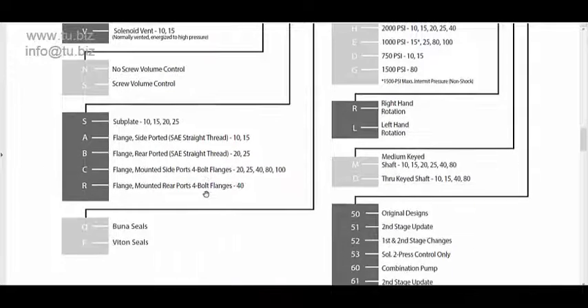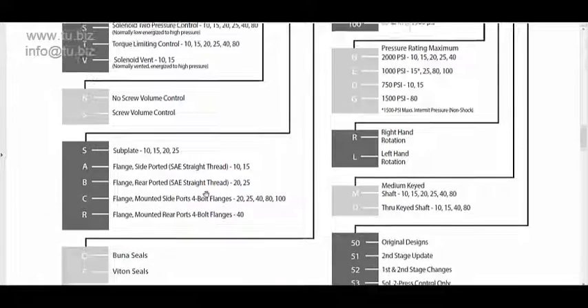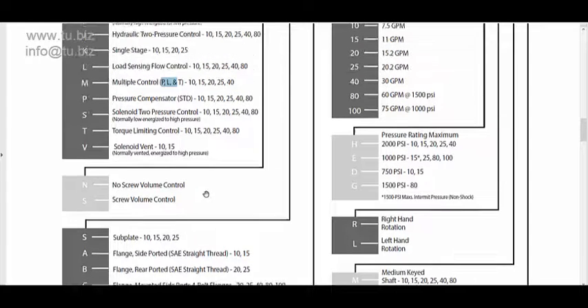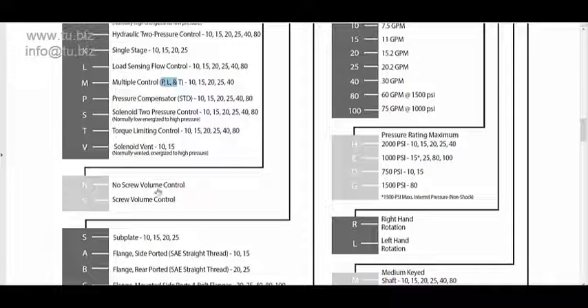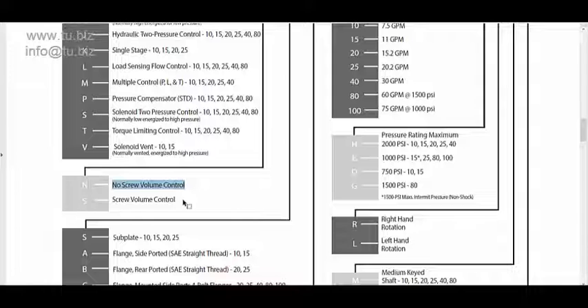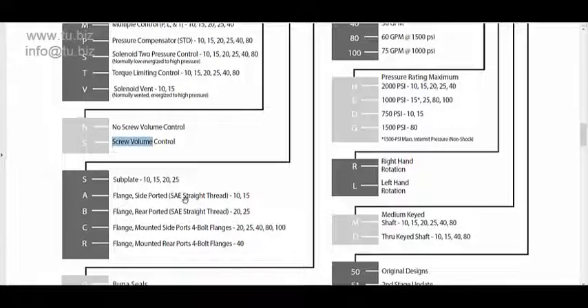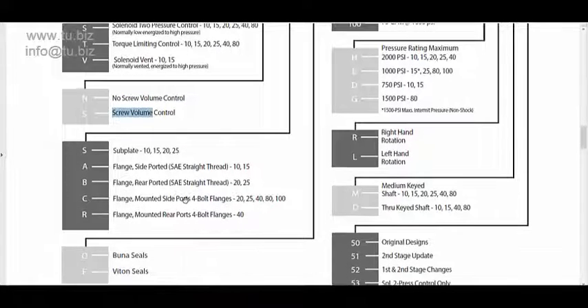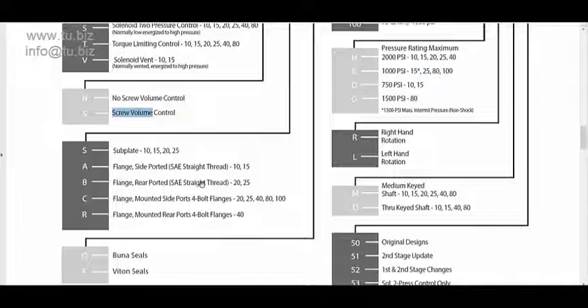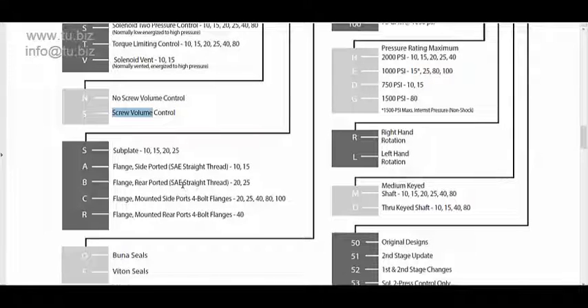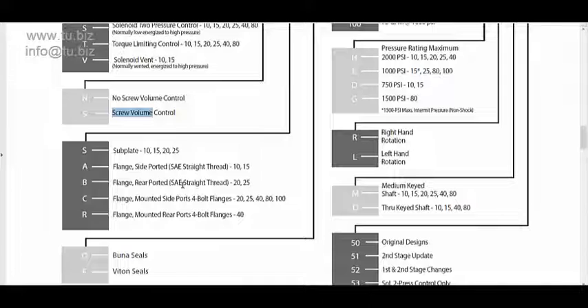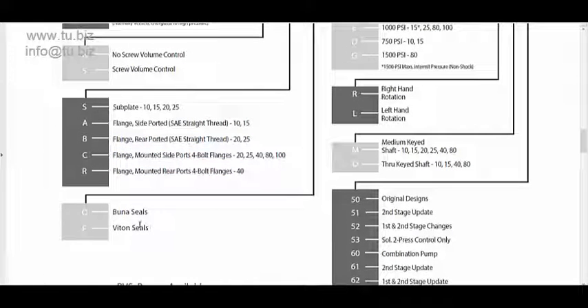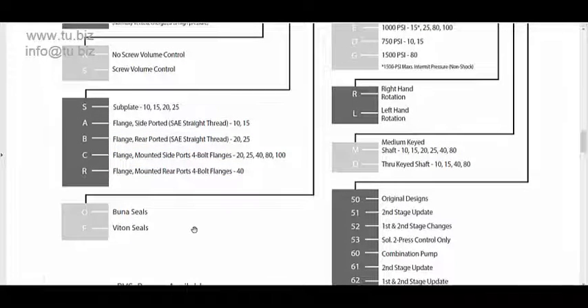Yet the pressures are medium to low pressure. Another feature of this pump is the screw for maximum volume control, so you can destroke the pump and lower the displacement, or you can have it with no volume control. Then we move into the connections of the pump, basically SAE standard, nothing unusual over here, very standard connections. Seals available are Buna seals and Viton seals.